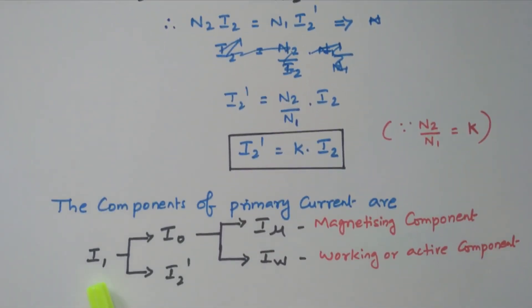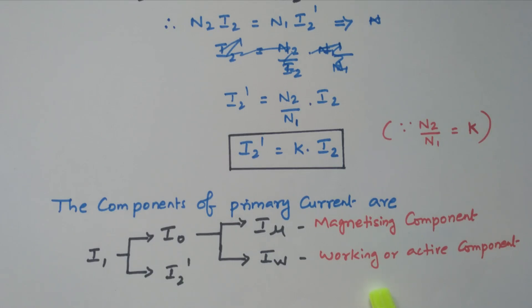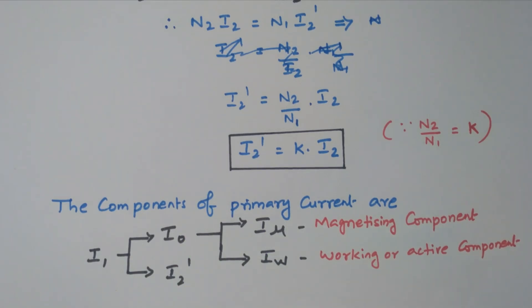The total primary current I1 is the vector sum of I0 and I2'. Under no-load condition we have I0; under loaded condition we have I2'. So I1 is the vector sum of I0 and I2'. The no-load current I0 itself has two components: one is the magnetizing component Iμ, and the other is the working component IW, also called the iron loss component, which accounts for core losses. In this video we discussed what happens to the current and flux when the transformer is loaded.